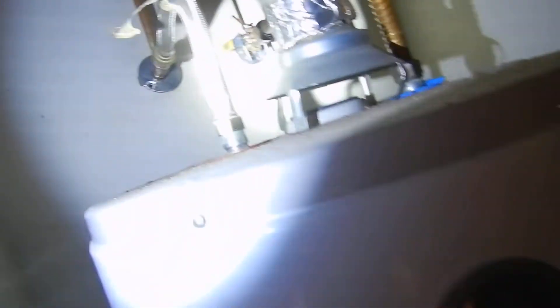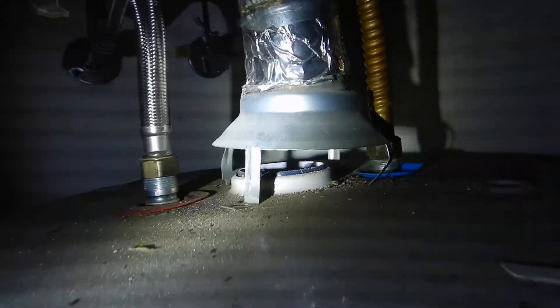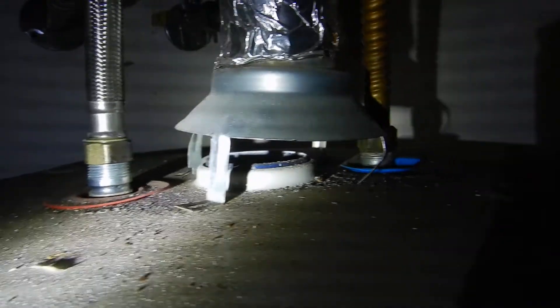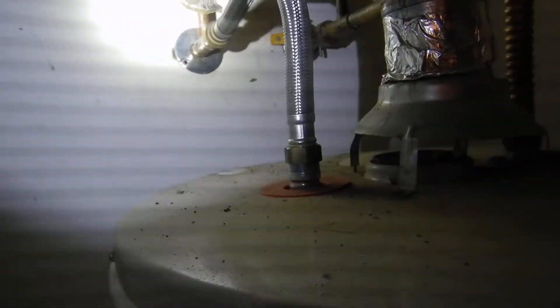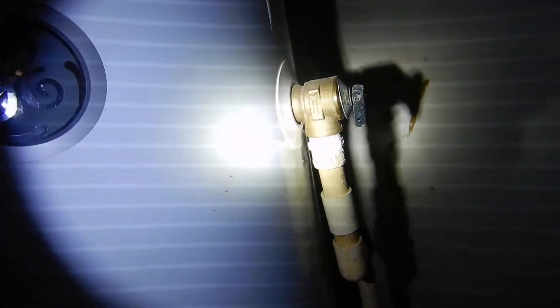We've got the water supply lines and distribution lines. Okay, we have our dielectric unions there, but the flue cap doesn't fit right. And this piping is supposed to be insulated. And this is your temperature pressure relief valve, and it's supposed to be insulated. The drain line, no, okay, but it's supposed to be insulated.